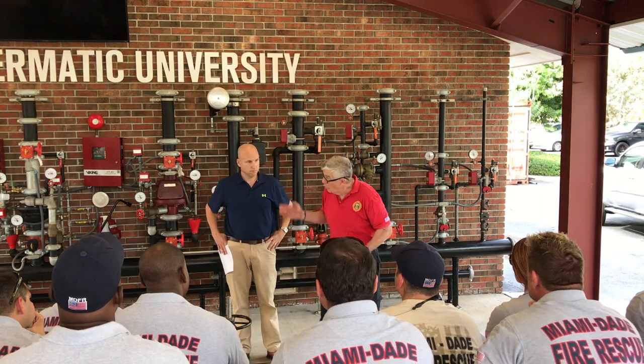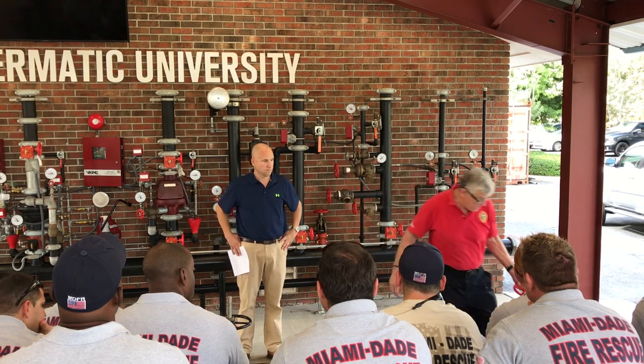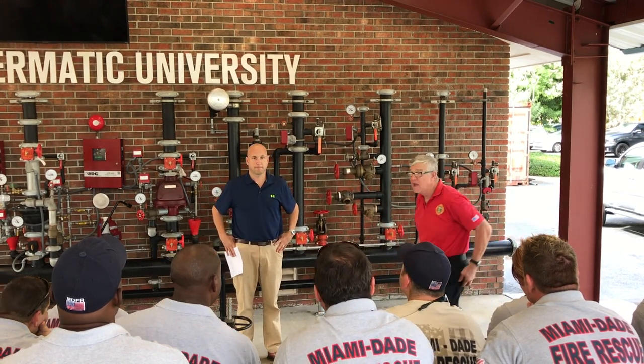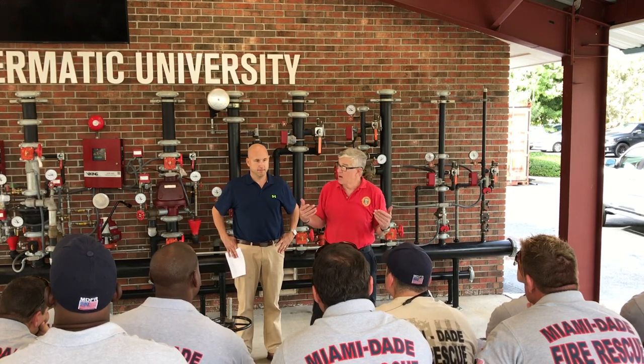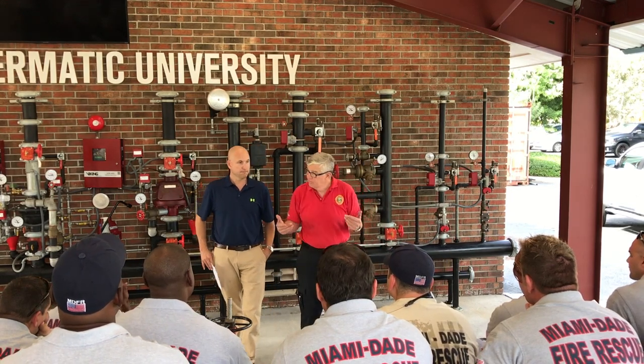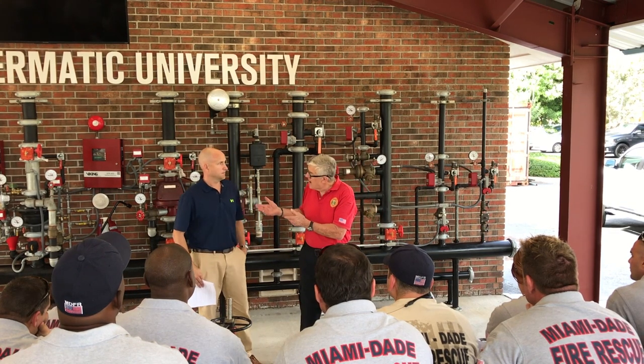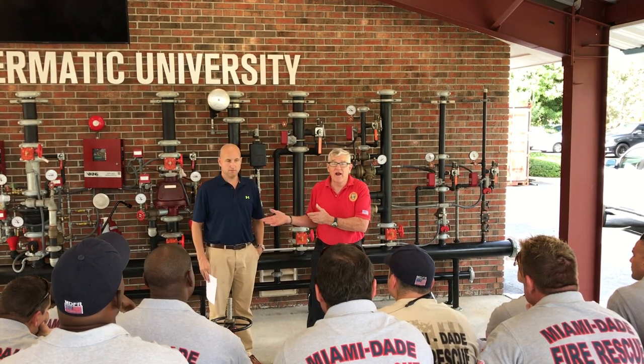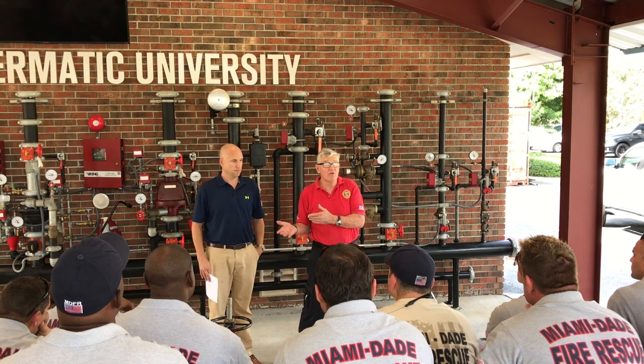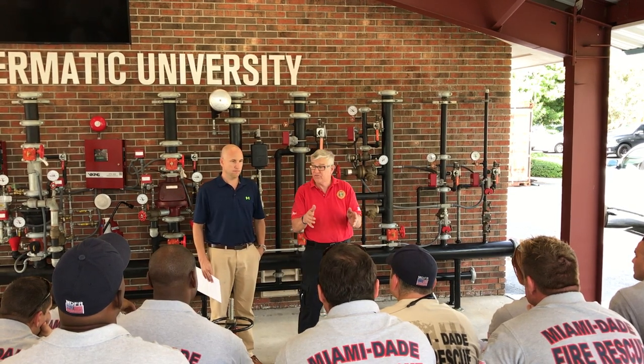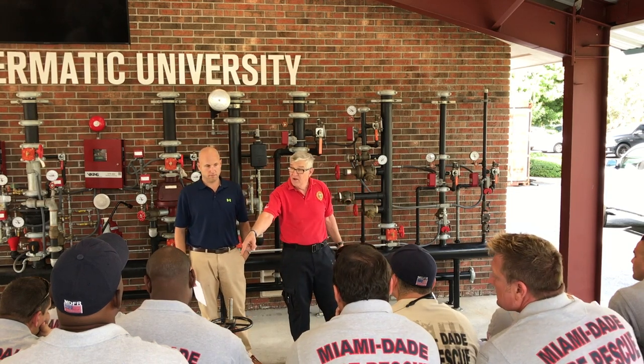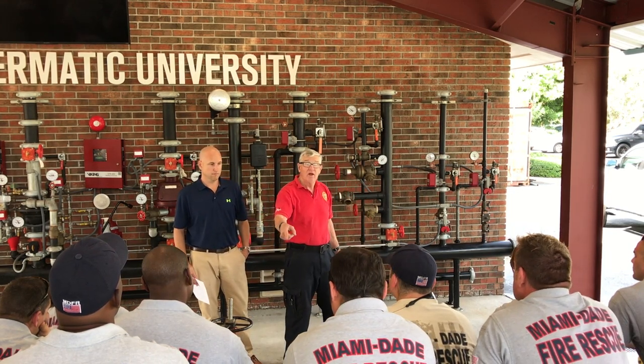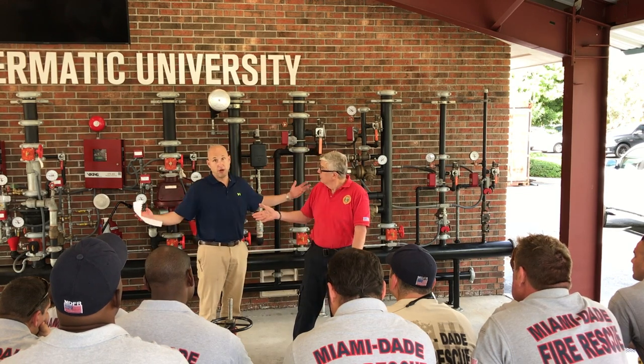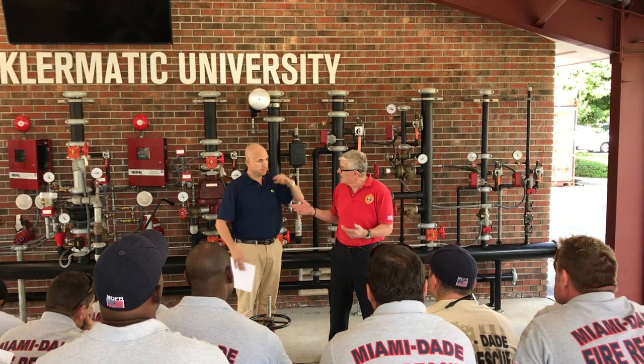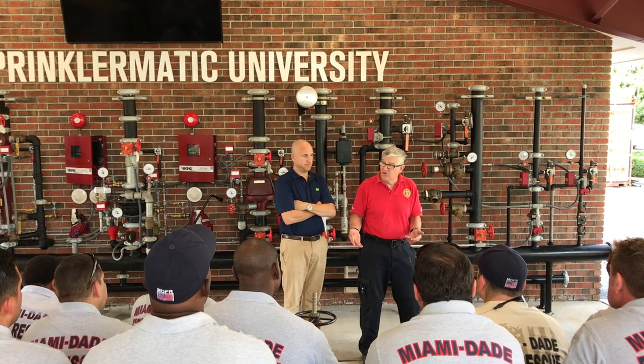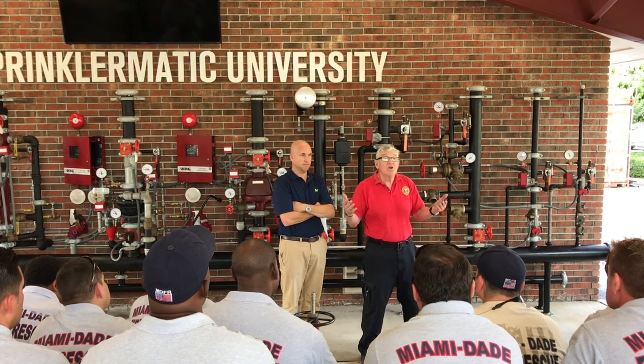Now, Will is trying to close the disconnect between the fire suppression equipment industry and the fire departments because we have a vested interest. If a pressure reducing valve fails, it's a black eye on their part in their industry, although they will assume no liability if you are not testing it in accordance with those provisions of NFPA 25. But we're still in the boat, guys. We both have skin in the game with this. And if the valve fails, you're not going to like it, and it could kill us.